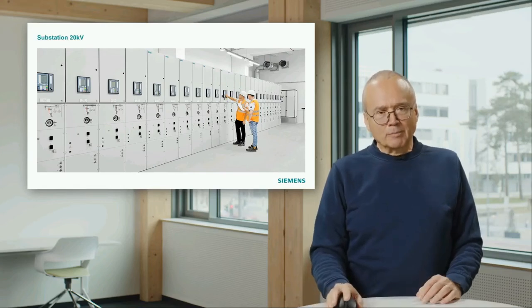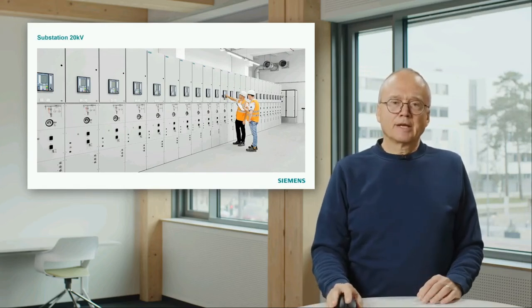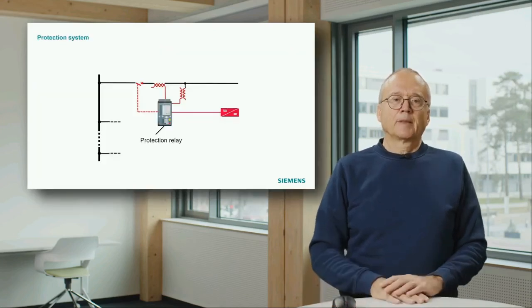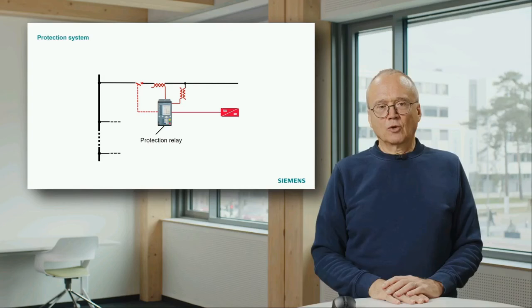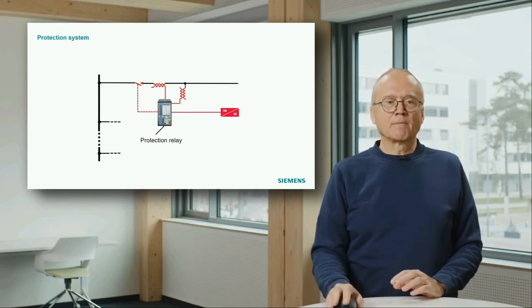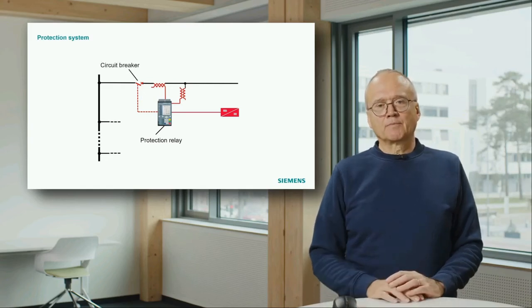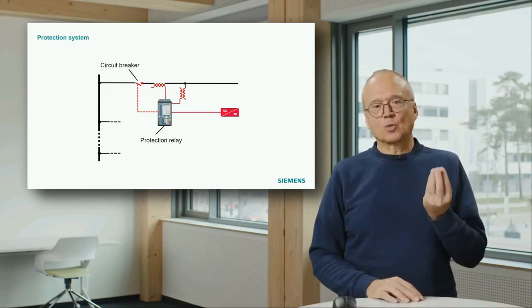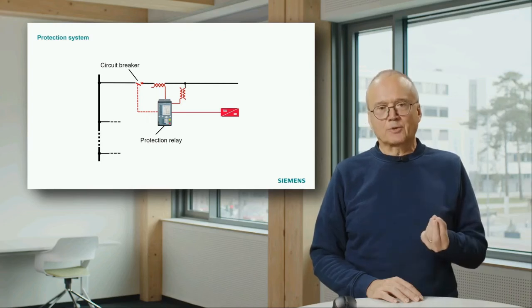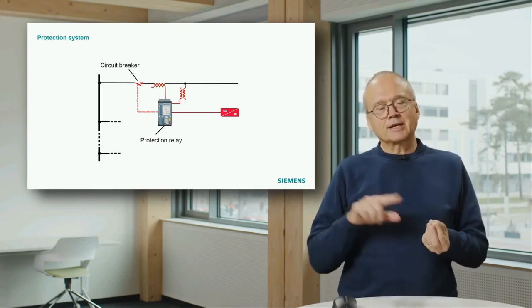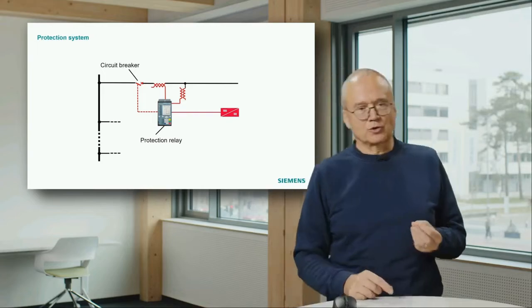If we now look a bit more in detail into such a feeder, it looks like this. You see on the left-hand side again the bus bar, and then I illustrated one feeder a bit more in detail. You see here the circuit breaker. That is the device which is really able to interrupt the short circuit current in case the line has a short circuit.